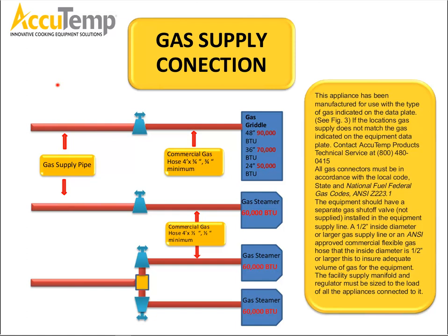And this is a little example of how AccuTemp likes to see their equipment connected, and it's probably standard across the board with other manufacturers. So we have our griddle, we have a 24-inch, a 36-inch, and a 48-inch. We like to see the pipe, and obviously each piece of equipment should have its own shutoff valve, and the actual size of the line going to the griddle, for us, is a minimum of 3/4 inch.